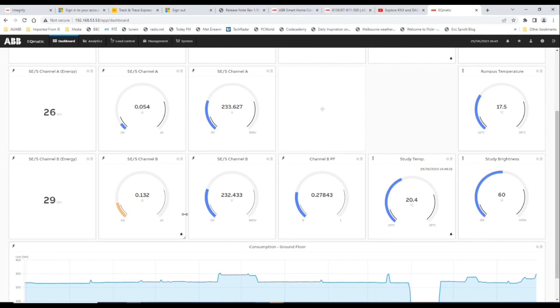You can do all sorts of stuff here with these alarms - decide when you want alarms, what schedules, severity of alarms. There's quite a lot you can do to set up and control and manage this dashboard. It's configurable for each user, so each user can come in and set their own information up here - really quite useful. That alarm function is available on the KNX version only, so be careful - don't get the Modbus version expecting you'll have it.